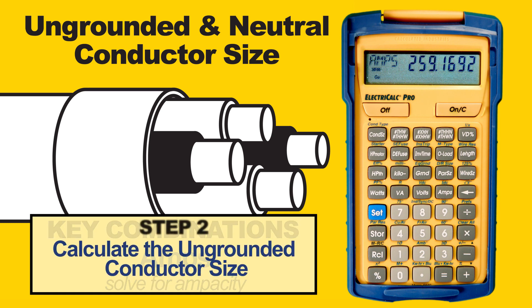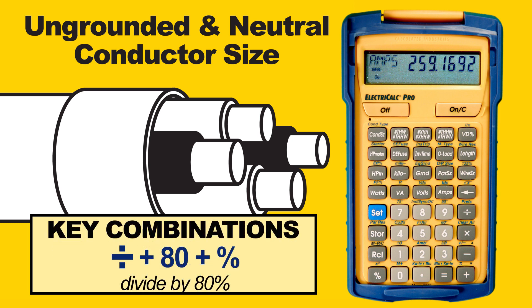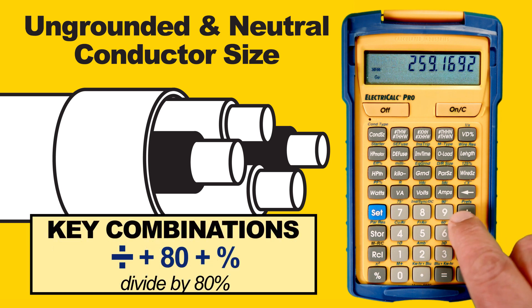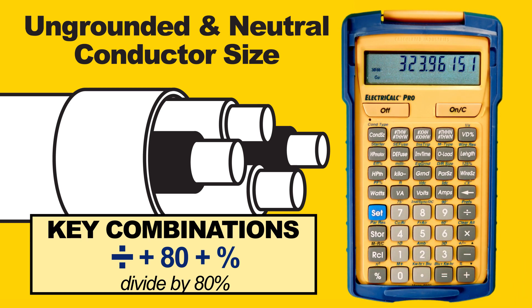The second step is to calculate the ungrounded conductor size. Since there will be four conductors in that RMC conduit, we have to adjust the ampacity by 80%, so we take this number and divide by 80%. The answer is 324 amps for the ungrounded conductors.